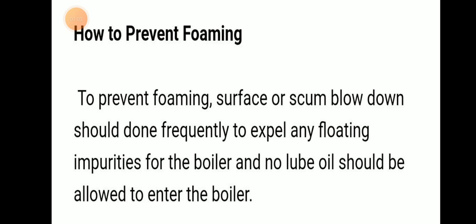To prevent foaming, surface or scum blowdown should be done frequently to expel any floating impurities from the boiler. Also, no lube oil should be allowed to enter the boiler.